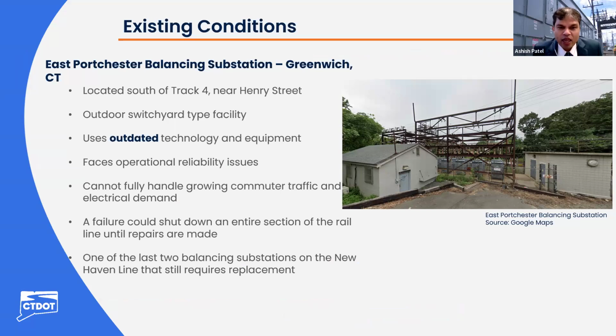This picture was taken at the end of Henry Street on the south side of the New Haven main line. It shows the existing balancing substation brick and mortar building. On the right side is what acts as a control house. The railroad training building is shown on the left side of the picture. The existing balancing substation is an outdoor ready switchyard type balancing substation. This substation does not receive utility power. It acts as a voltage balancing substation. So one set of railroad aerial traction power wires are tied to the east of the balancing substation, and another set of railroad aerial traction power wires are tied on the west side of the balancing substation.